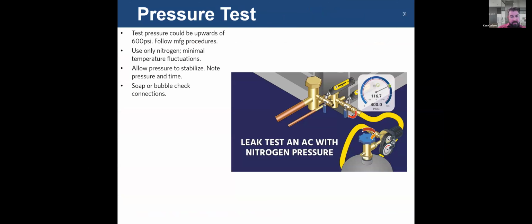So you've done your flaring, you've made all your connections on your line sets. You need to pressure test your system to make sure you have no leaks. The manufacturer's installation manual will tell you what that pressure needs to be. A lot of times it's 1.5 times working pressure. Working pressure varies. Some manufacturers will require up to 600 psi for a pressure test. Again, that varies by manufacturer. Use only nitrogen. Nitrogen does not fluctuate as much as air, and especially refrigerant. This way, when you leave it under pressure for a prolonged duration, whether it's a couple hours or a day, depending on what the manufacturer recommends, you won't see fluctuations in pressure due to temperature. You can be confident that your pressure is being maintained.